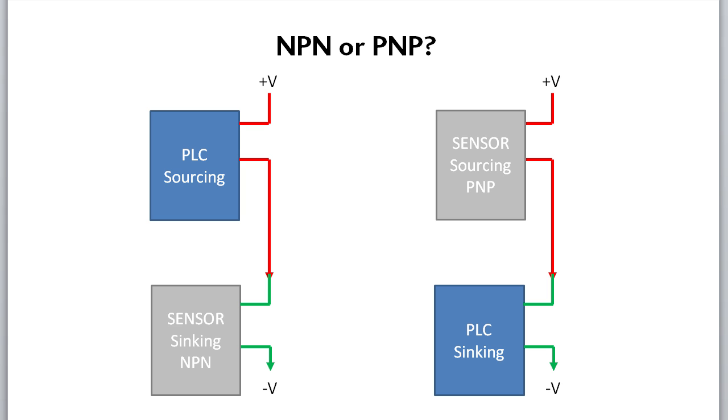If the sensor is sinking current to the negative supply, then it is NPN – think of N for negative. If the sensor is sourcing current from the positive supply, then it is PNP – think of P for positive.